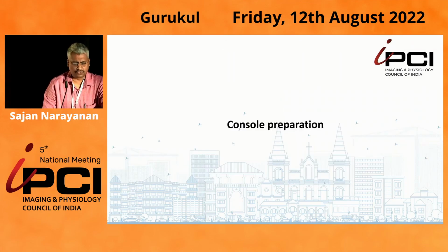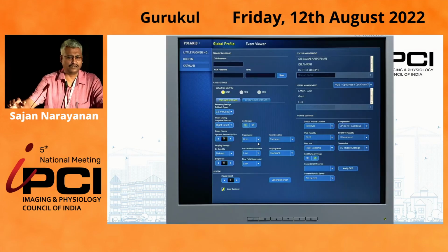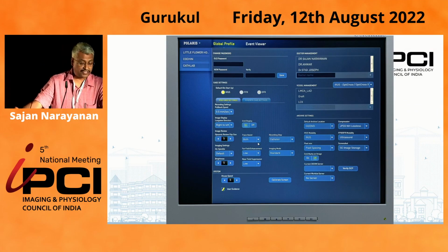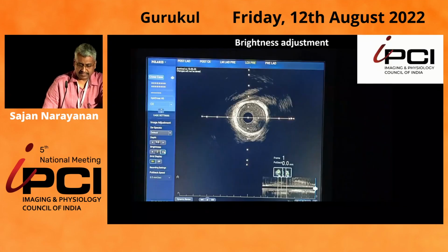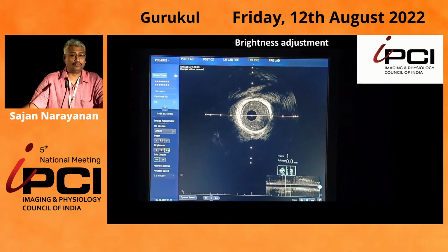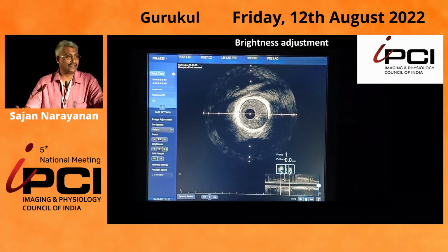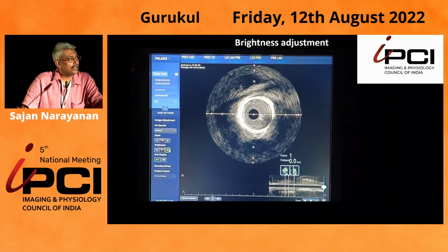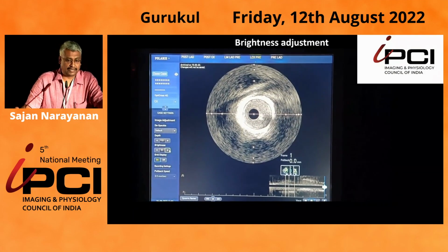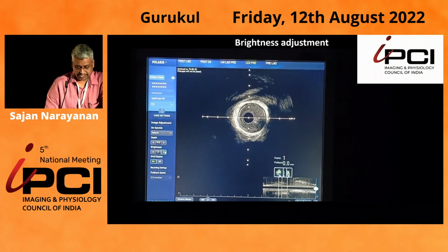Now we'll come to the console preparation. This is how a console looks like. You have different parameters. You can set the recording speed. You can either record at 0.5 millimeter per second or 1 millimeter per second. You can choose which way it has to be displayed, and most importantly, you can adjust the brightness. Because if it is too bright or too dark, then that can interfere with the image acquisition, and there can be false dropouts, and that can interfere with your decision.